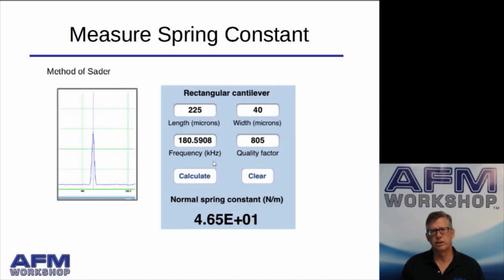So what people like to do is you can use what's called the method of Sader. You can look that up on the internet, and you can go out and get a spectrum analyzer. You can buy these on the internet for not very much money, and you can measure the resonance frequency and get the thermal spectrum of the probe. And then there's different calculators out there, and what you do is you put in the length of the cantilever and the width of the cantilever, which you can measure with your video microscope that's in your AFM. Just make sure it's calibrated, and the resonant frequency and the quality factor, which you measure with the spectrum analyzer, and you can calculate the force constant. And so this force constant for this particular cantilever came out to 46.5 newtons per meter. So this is something that you can do quite easily.